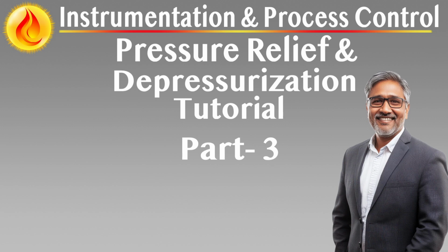Disposal of thermal expansion relief valve, TERV. TERV discharges should ideally return to the process system, a dedicated closed relief header, or a safe storage or handling system. If no closed path is viable, and if permitted by local regulations, TERVs may discharge into open drainage systems. However, this is restricted to non-toxic, environmentally benign fluids. For toxic or hazardous fluids, closed containment is mandatory.